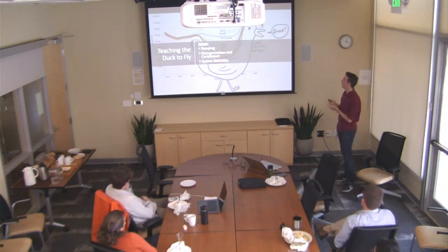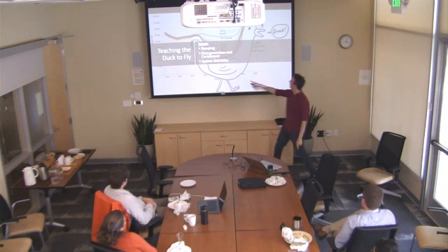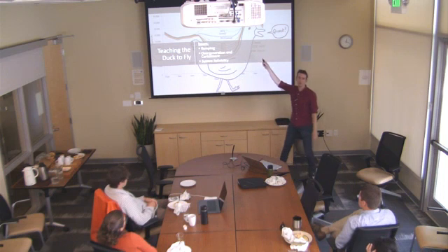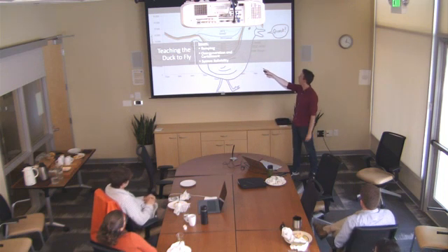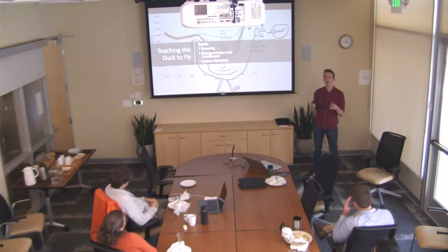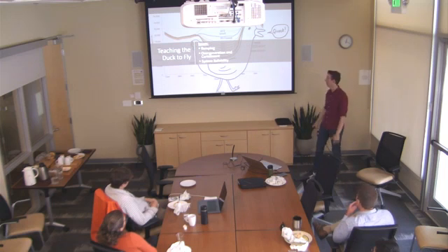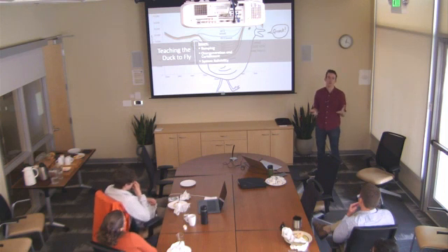So the main issues are ramping. During this evening ramp, that's really hard for system operators to meet. Overgeneration and curtailment. Overgeneration has to do more with the local level, the fact that on some specific distribution feeders, the amount of solar energy actually exceeds the amount of demand, and you're feeding power back into the grid, which causes reliability issues. And then curtailment has to do with just the fact that we're wasting available solar capacity. We have to turn it off.